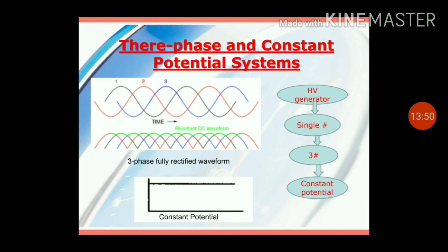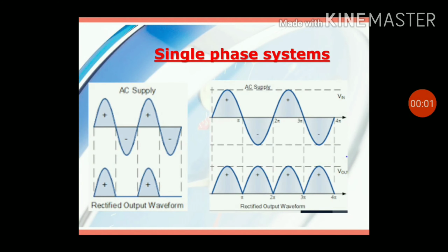Advantage of high frequency generators: they require less exposure time, nearly half or two-thirds compared to single phase. They are two times more efficient and produce sharper, better quality images than single phase or three-phase generators.